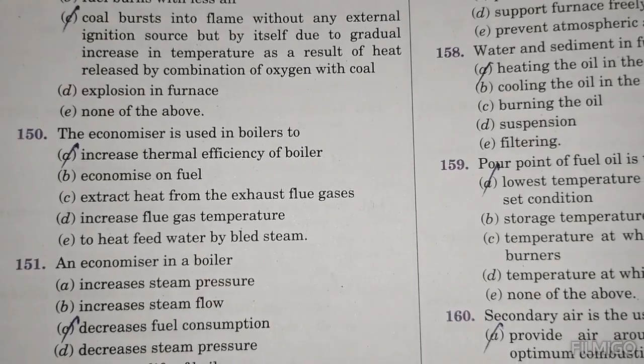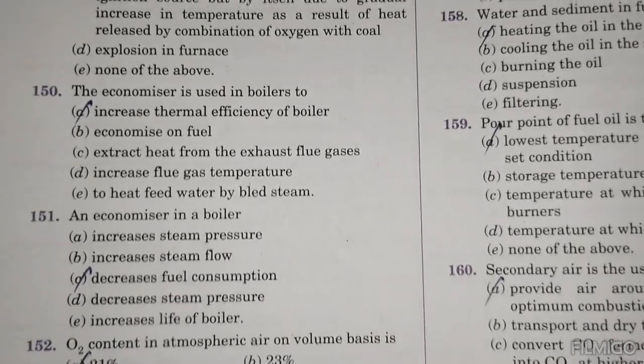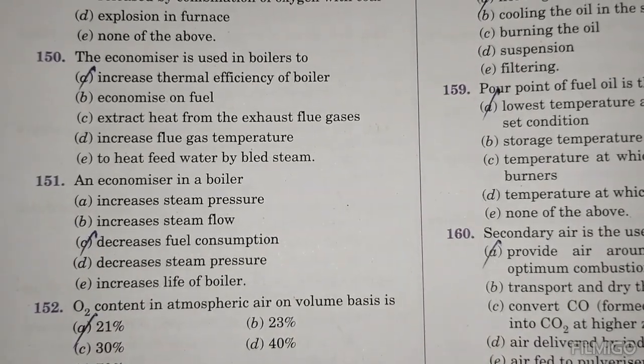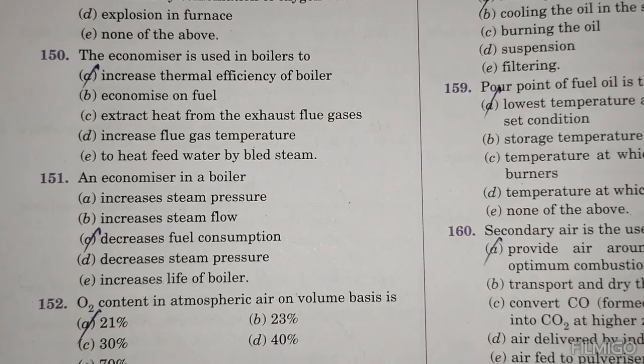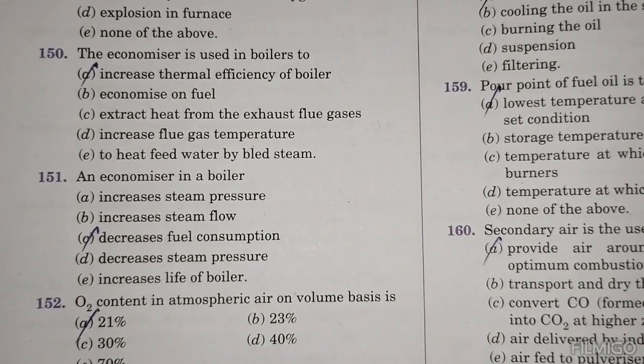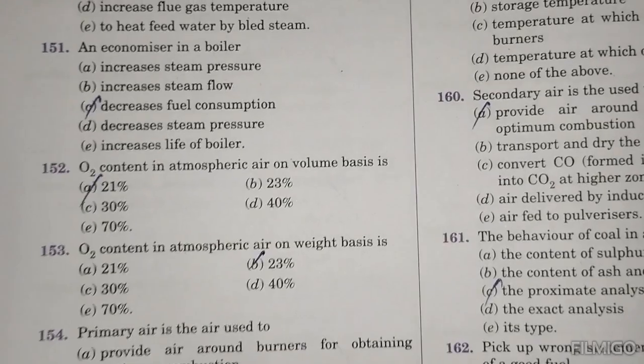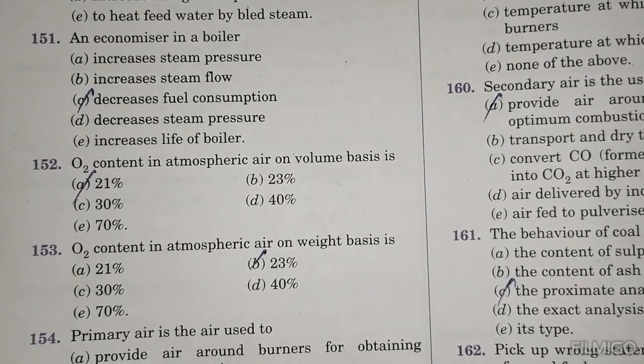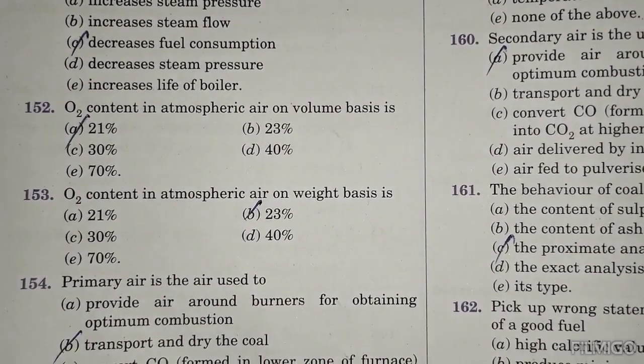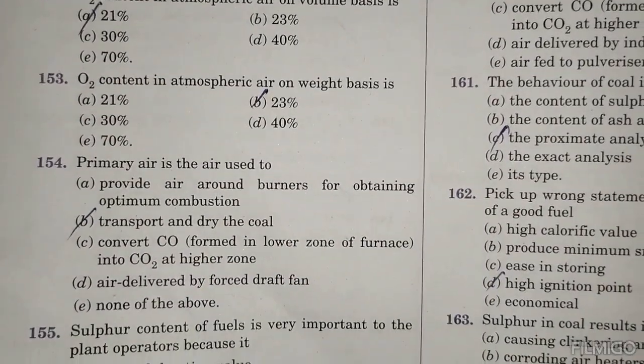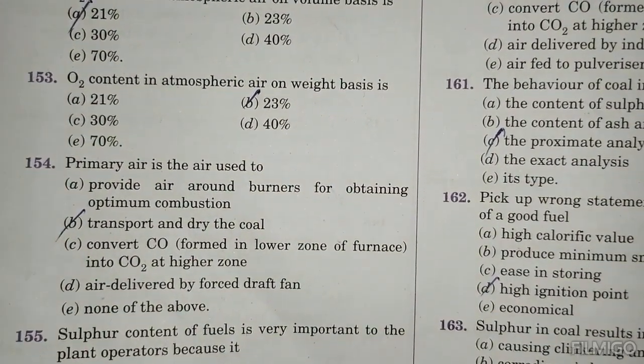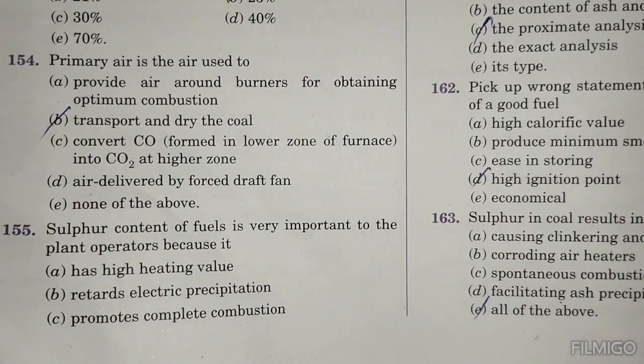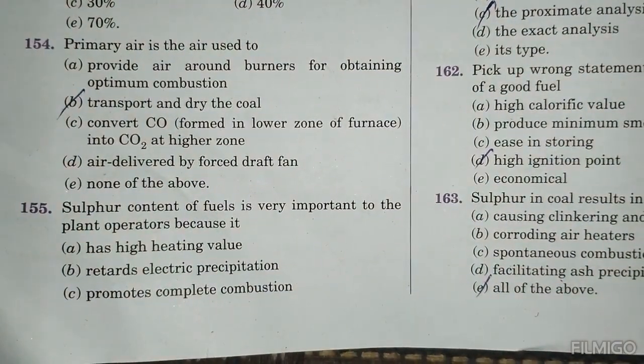The economizer used in a boiler increases the thermal efficiency of the boiler. An economizer used in boilers increases thermal efficiency of the boiler. An economizer in a boiler gives decrease in fuel consumption. O2 content in atmospheric air on a volume basis is 21%. O2 content in atmospheric air on a weight basis is 23%. Primary air is the air used to transport and dry coal. Sulfur content of a fuel is very important to plant operation because it has a highly corrosive effect.